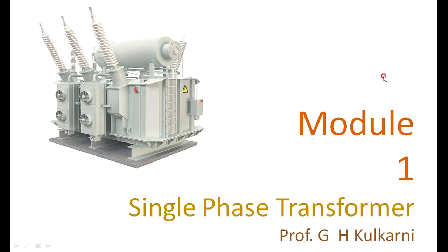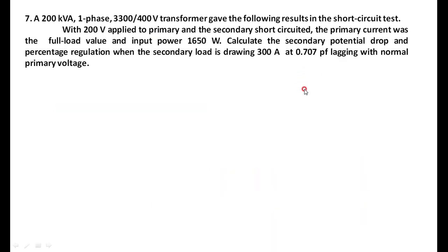We will continue with the numericals on the equivalent circuit, finding the parameters of the equivalent circuit, and the regulation and efficiency of the transformer. We will take the next numerical: a 200 kVA single-phase 3300/400 volt transformer with the following OC and SC test results. With 200 volts applied to the primary and the secondary short-circuited, the primary current was the full load value, and the input power is 1650 watts. Calculate the secondary potential drop and the percent regulation.